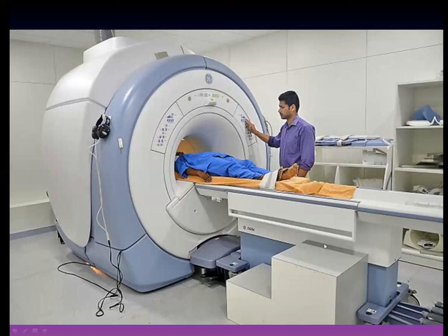For the technologist, if he wanted to stand in the room while he was imaging, he certainly could because there's no radiation. So they tend to walk in and out of the room to check on the patient. But again, remember, this is a huge magnet, so we don't want any metal in the room at all. So the technologist has to be really careful not to have any metal on them. If they come in there with their keys or their cell phone or something like that, it's going to get pulled inside that magnet.